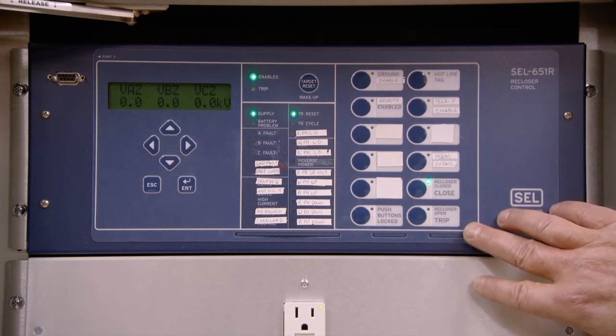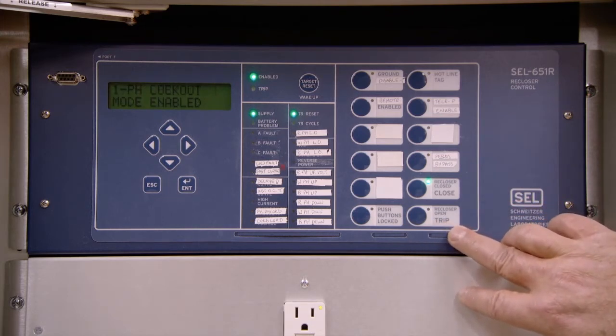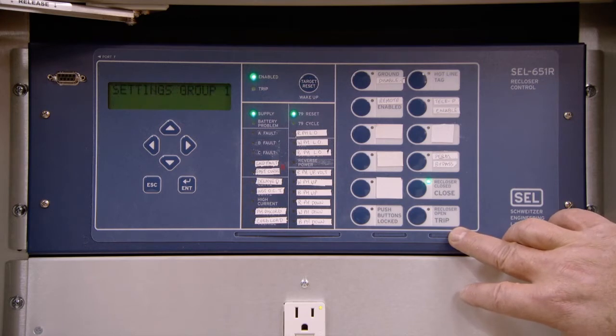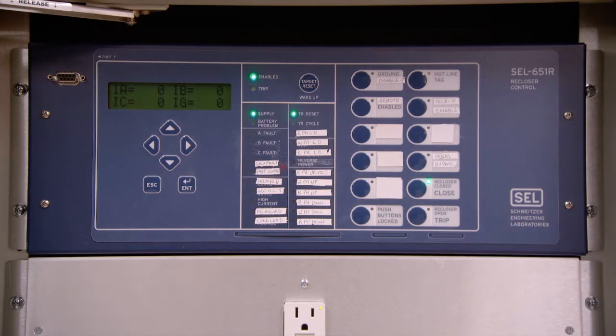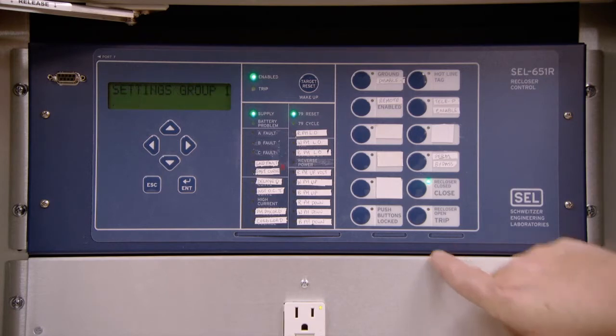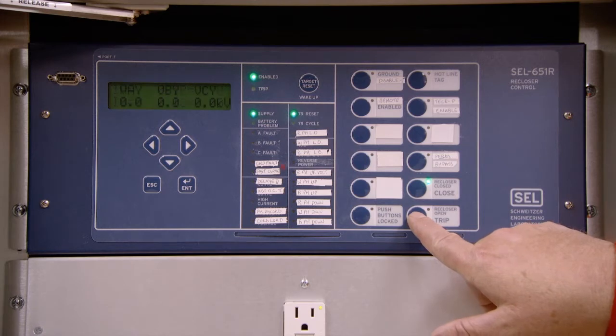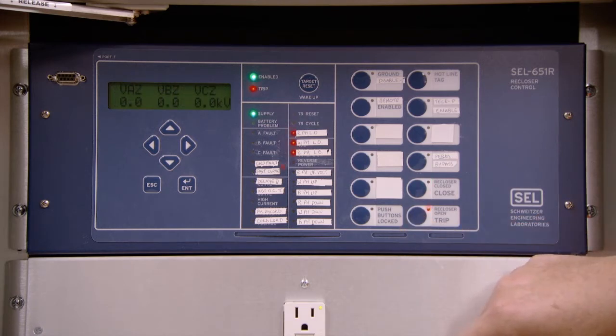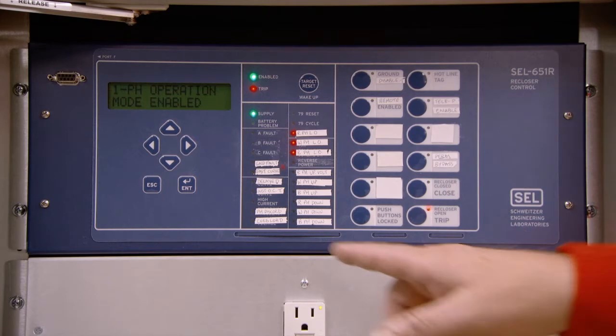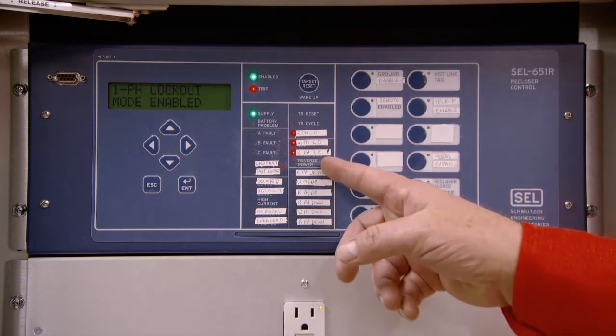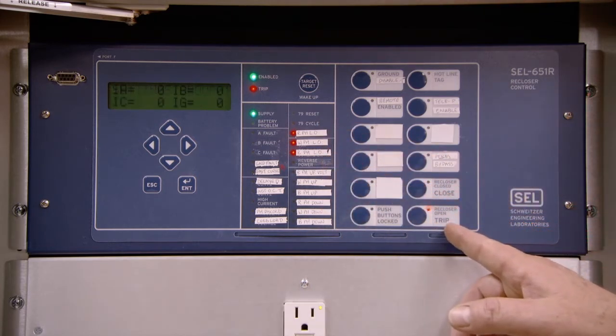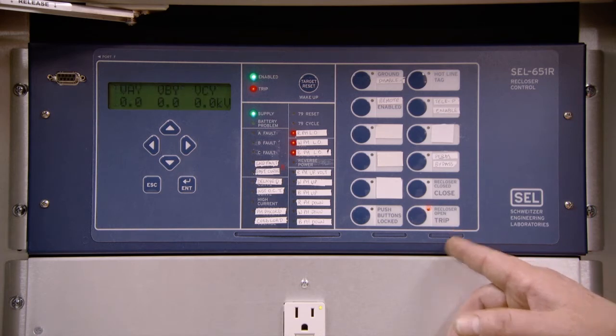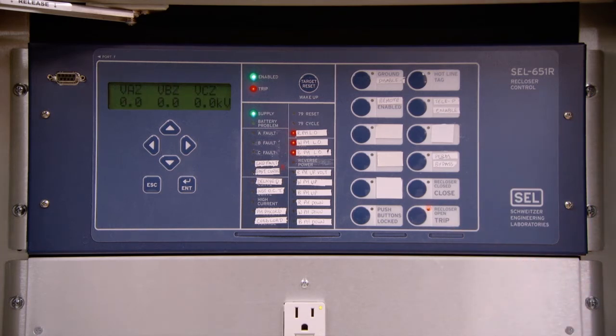If there is a need to set up for either three-phase or single-phase operation, the 651R can be set up for gang operation or individual operation of the reclosers. If you were to push the trip button itself, it will trip all three phases, no matter what the setup. If we were to manually trip the controller, you would see indicated on the left side of the panel that all three phases are open and the three red LEDs illuminate to indicate that the recloser has been tripped. It is now in a tripped state.